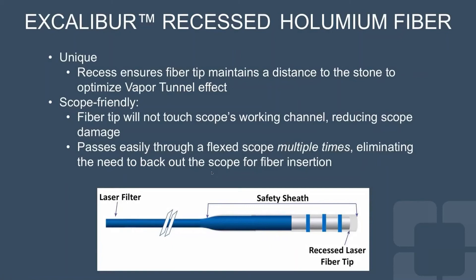To support this, they have developed the Excalibur fiber — a recessed fiber tip optimized for use with the vapor tunnel effect. The laser fiber tip is recessed within a safety sheath, creating the space needed for the vapor tunnel effect to function even when the sheath contacts the stone. Additional advantages include that the fiber tip won't damage the scope's working channel due to no direct contact, and it passes easily through a flexed scope multiple times, eliminating the need to back out the scope for fiber insertion.